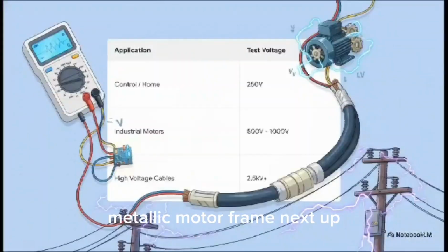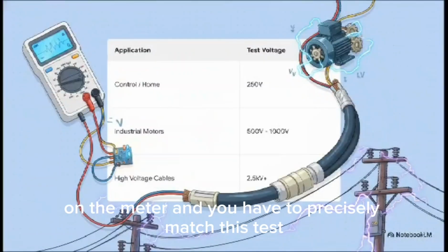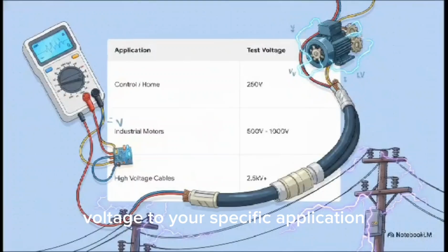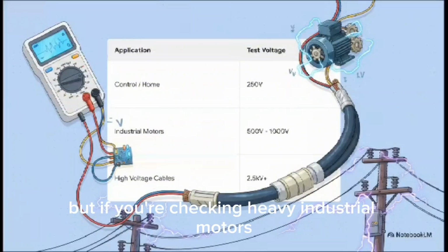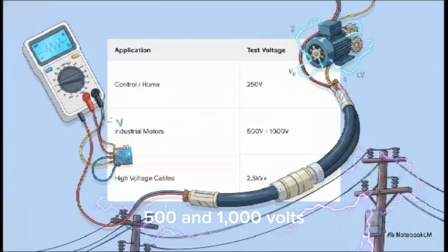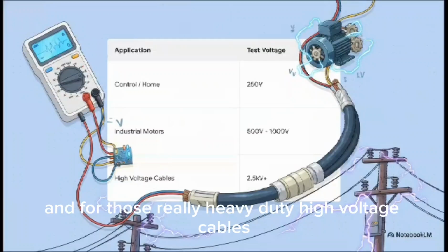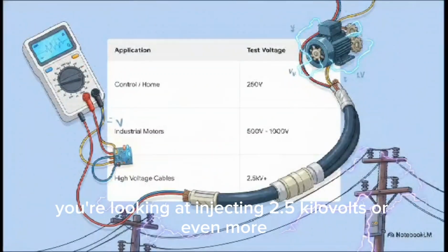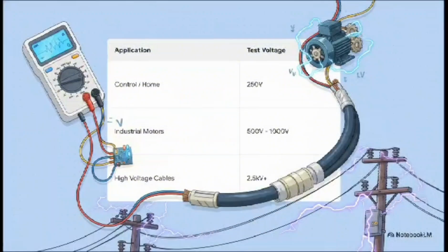Next up, you have to select the correct test voltage on the meter, and you have to precisely match this test voltage to your specific application. So for low-level control circuits or just your standard home wiring, you're only going to use 250 volts. But if you're checking heavy industrial motors, you're going to dial that up to somewhere between 500 and 1,000 volts. And for those really heavy-duty, high-voltage cables, you're looking at injecting 2.5 kilovolts or even more. But please, I need you to burn this massive warning into your memory right now. Applying 1,000 volts of direct current to the wrong thing will instantly and permanently destroy sensitive modern components.